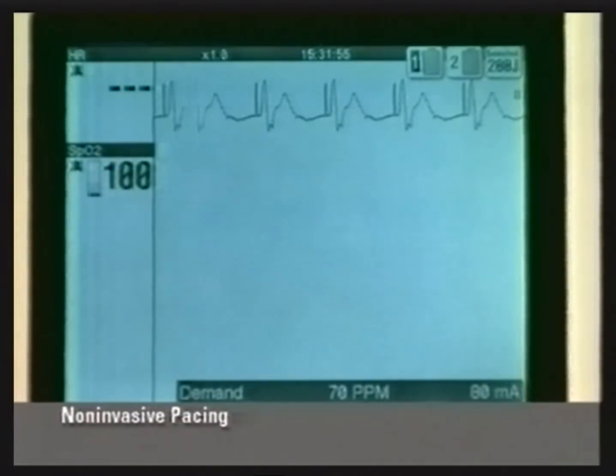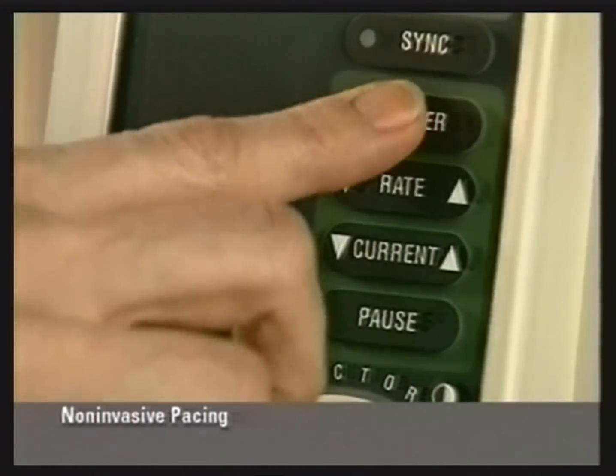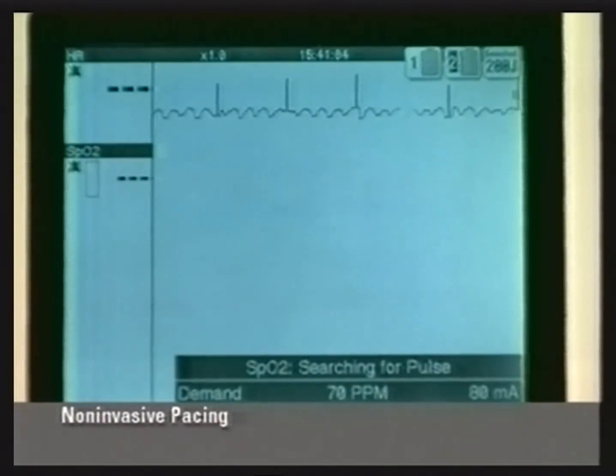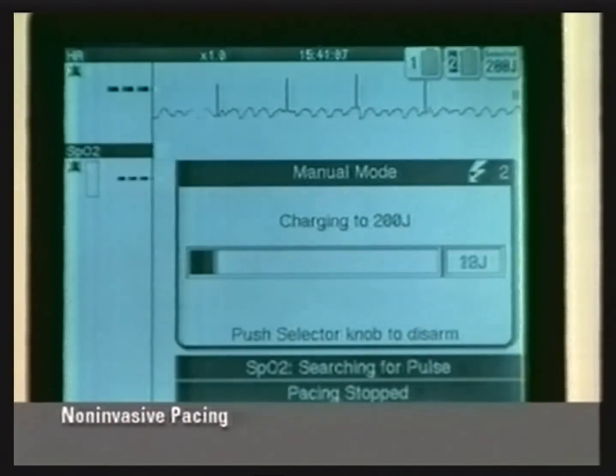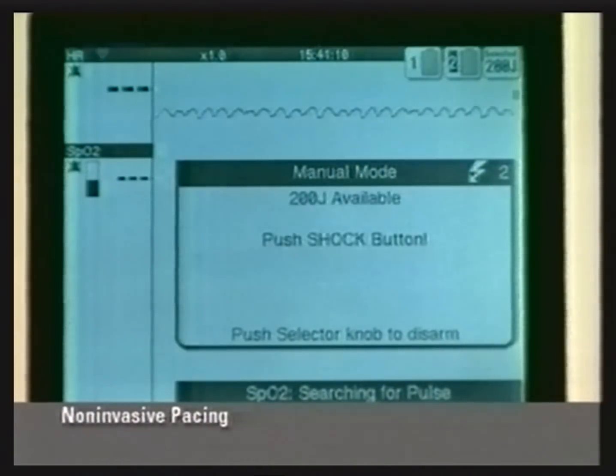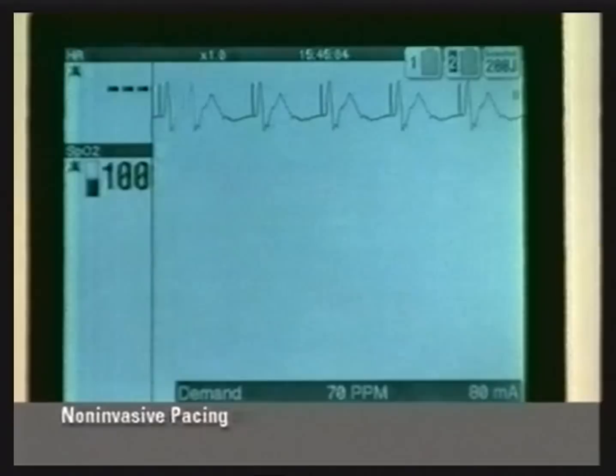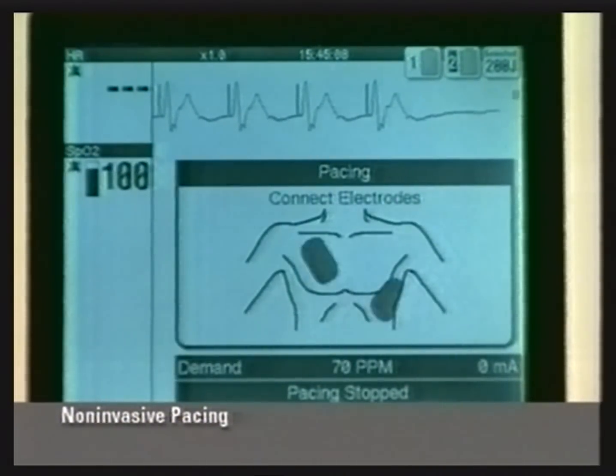To stop pacing, reduce current to 0 or press pacer. If defibrillation becomes necessary, press energy select or charge. Pacing automatically stops. Pacing therapy stops if the pacing cable or therapy electrodes disconnect. A message and alarm tone sound.